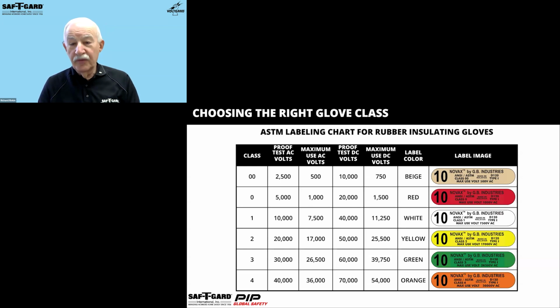Take care to choose the correct rubber insulating glove for the task at hand and the level of electrical exposure. Those gloves are all going to have a label on them that is color-coded and identifies the class and the maximum use voltage at AC voltage, which is the most common. Rubber insulating gloves are typically manufactured in sizes 8 through 12, often in half sizes, and some manufacturers offer gloves in sizes as small as size 7 and even as large as size 13. In addition, rubber insulating gloves are available in different cuff lengths of 11, 14, 16, and 18 inches, which vary according to the glove class and the hazard.